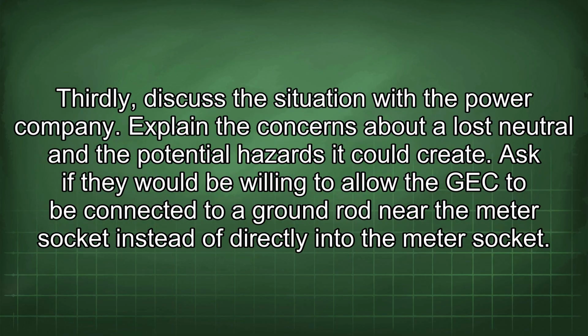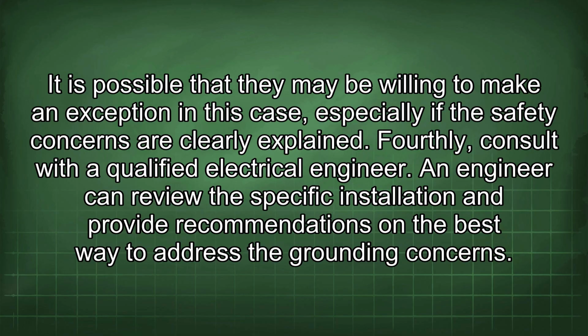Thirdly, discuss the situation with the power company. Explain the concerns about a lost neutral and the potential hazards it could create. Ask if they would be willing to allow the GEC to be connected to a ground rod near the meter socket instead of directly into the meter socket. It is possible that they may be willing to make an exception in this case, especially if the safety concerns are clearly explained. Fourthly, consult with a qualified electrical engineer.